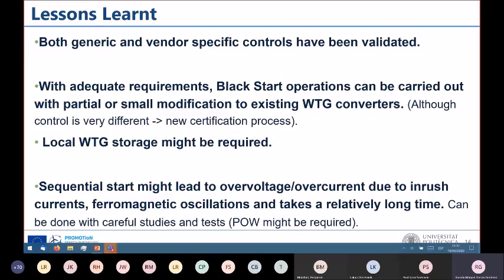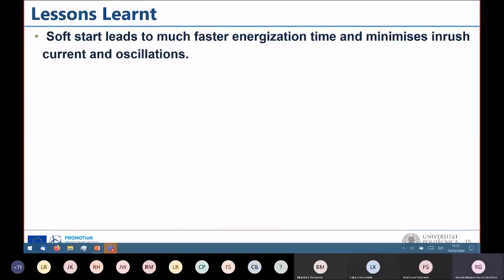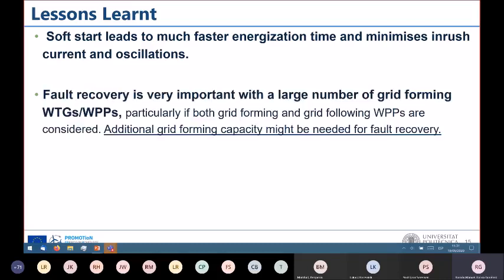Sequential black start is possible, but might lead to overvoltages and overcurrents due to inrush. We have to be able to study those cases very carefully. And soft start always leads to much faster energization time and minimizes inrush currents and oscillations. These conclusions are valid both for HVAC and for HVDC connected wind farms. Fault recovery is very, very important with a large number of grid forming wind turbines, especially if in some cases the grid forming capability is being provided by some wind farms that are connected to other wind farms in close proximity, which are grid following.